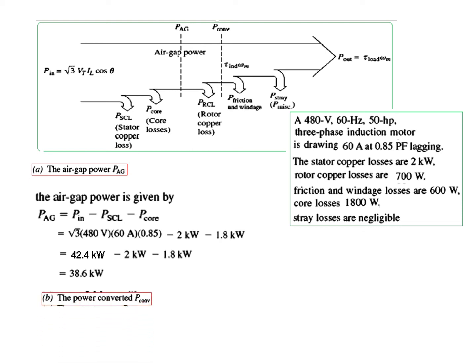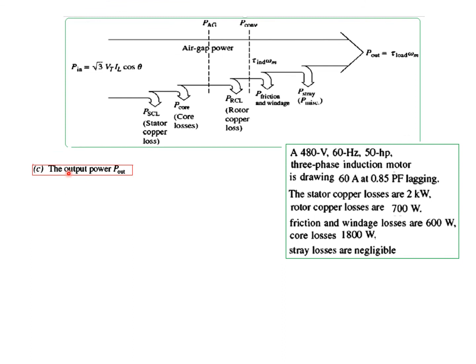Next is the power converted. We subtract the rotor copper loss from the air gap power: P_converted = P_AG − P_rotor_copper = 38.6 kW − 0.7 kW = 37.9 kW. For the output power, we subtract the friction and windage loss of 600 W (0.6 kW) and miscellaneous losses, which are 0. So P_out = 37.9 − 0.6 = 37.3 kW.